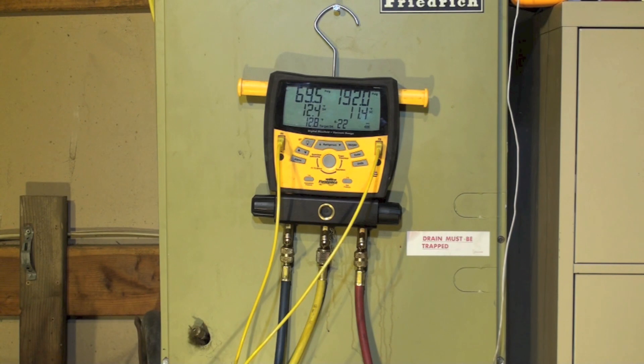Okay this was just an exercise in using your hand to charge these things at lower ambient. It's actually a little harder to do at low ambient. If the ambient is below 70 I don't even attempt it. But I started out here at about 75 I think about 77 right now and it's fairly viable. You know my suction pressure is about right and I was about an ounce off. This is fairly common for me to be about that far off if I'm lucky. Anyway that's the last one I'm going to do on checking superheat on a fixed orifice device machine, critically charged, just using your hand to check the superheat.